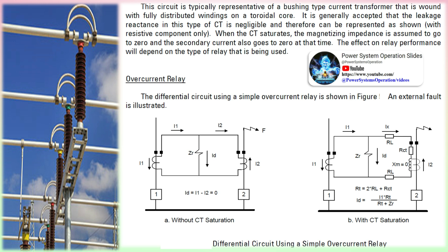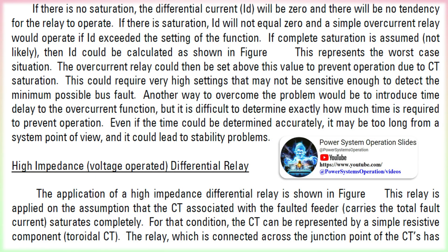CT saturation occurs when the flux required to produce the secondary current exceeds the saturation flux density of the core, as dictated by the physical dimensions of the CT. Whether or not any given current transformer will saturate is dependent on the following factors: CT ratio, core cross-sectional area, connected burden, magnitude of burden, presence and amount of remnant flux, amount and direction of DC offset in the current, and saturation flux density of the core steel. A typical case of CT saturation is for a fully offset current wave having a time constant of approximately 30 milliseconds.